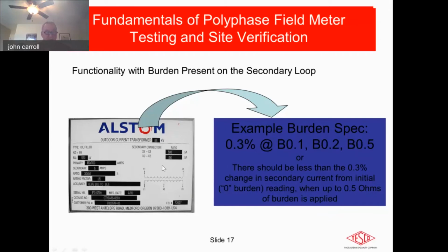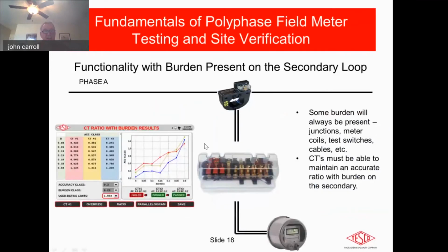These are tested in the factory when they're shipped to you, the user, and they'll give you parameters and specifications such as 0.3% in this case, its accuracy, at a burden of 0.1 ohms, 0.2 or 0.5. So it's multi-range. There should be less than 0.3% change in the secondary when you read it from the initial 0 burden reading when up to half an ohm is applied. To look at that in a little more detail, we'll move forward to how we do that, and I'll show you some of the measurements we took on this one.